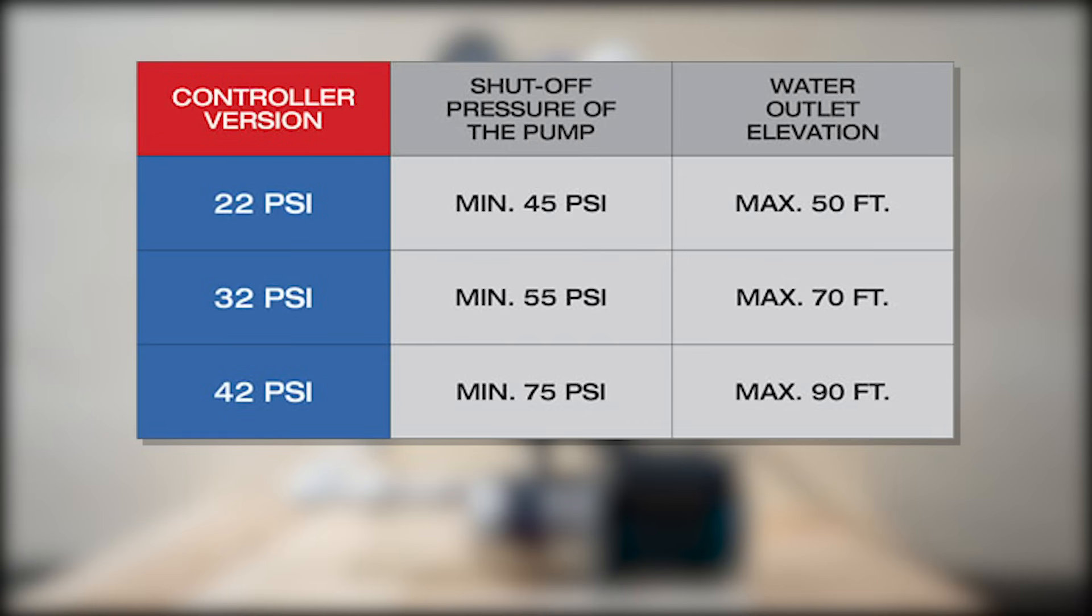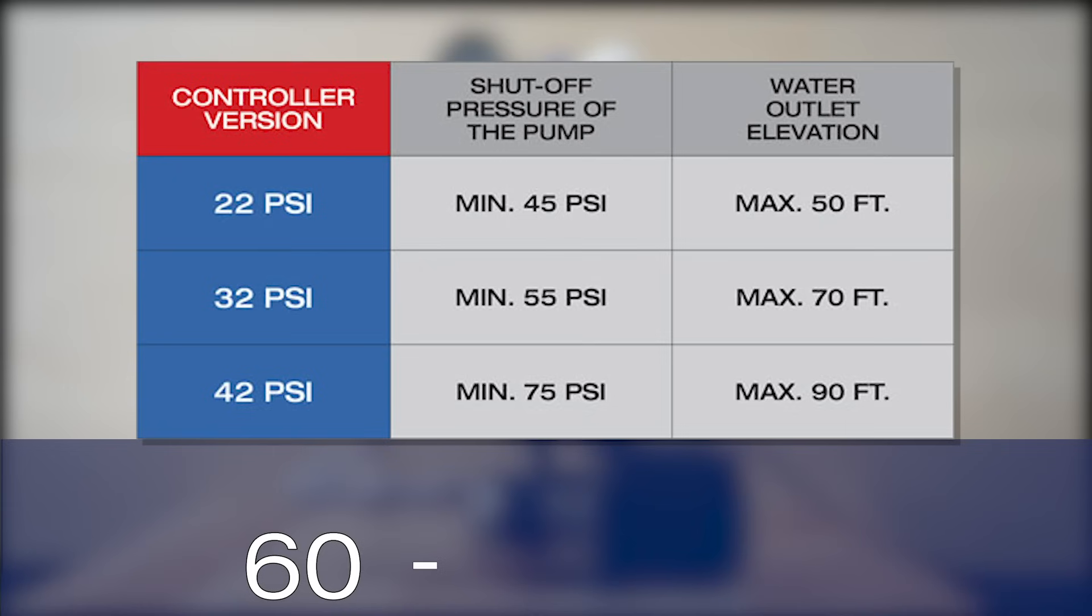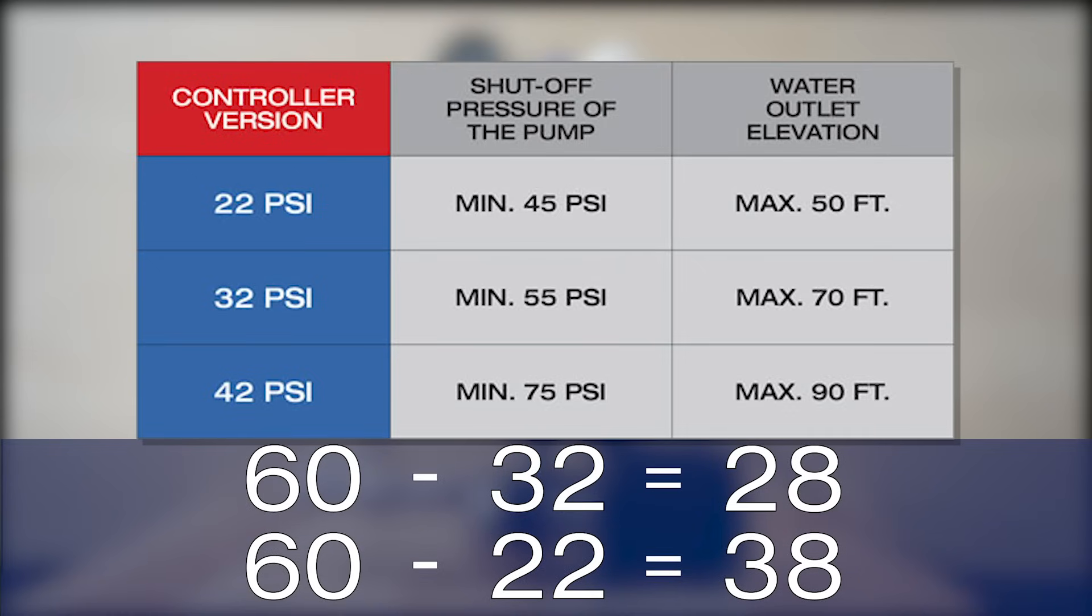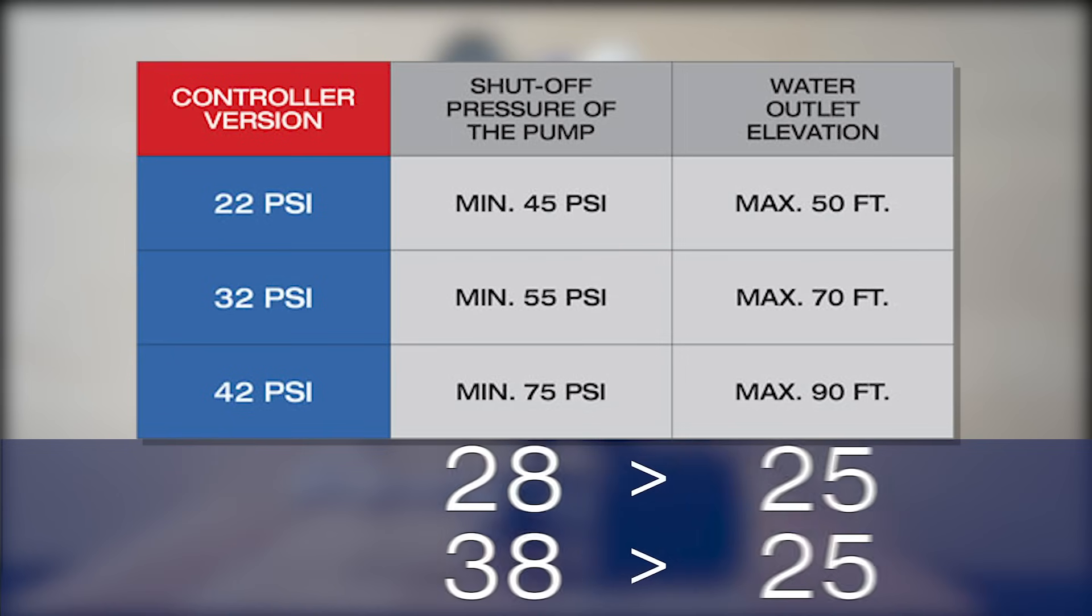For example, if the shut-off pressure of your pump is 60 psi, then the maximum starting pressure controller should be the 32. You could also use the 22 psi since the difference between the shut-off pressure is still greater than 25.